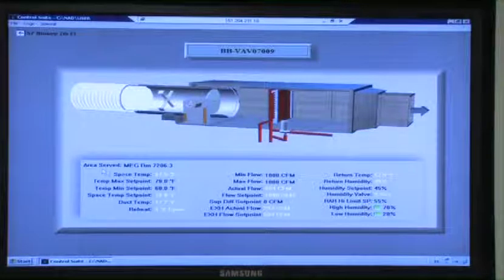So look at this one here. We got this served MFG room up here. These are going to be interesting things, guys, because these are the kind of things that we're not used to, that we have to make sure we get down pat. So max set points, okay. Duct reheats, reheat over, okay. Min flow 1,000, max flow 1,000. It's constant volume.